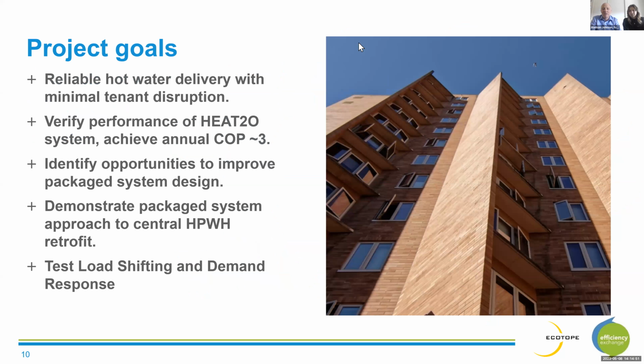So the goals of the project were to deliver reliable hot water with really minimal disruption to the tenants. They shouldn't really have known that their water heating system was being replaced, other than some feel-good announcements about the fact that it's using a third as much energy as it used to. We wanted to verify the performance of the HEAT2O product, and we were shooting for an average annual system COP of about 3.